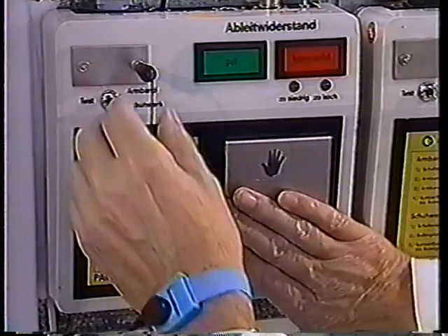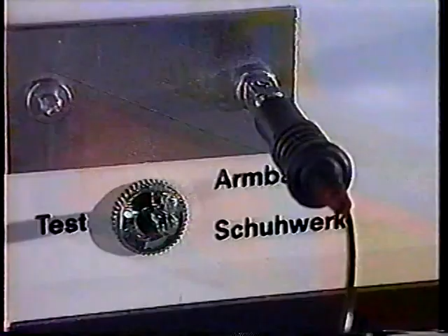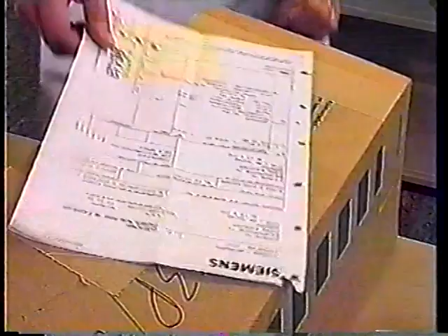In special cases, instructions may be given to wear dissipative finger cots or gloves. The most important item here, however, is the wrist strap, which should always be tested before entering the labeled EPA. As should the ground resistance of the footwear. A heel strap like this one is available for visitors. Of course, we sometimes have problems observing these regulations, but daily routine causes even the most reliable individuals to forget the occasional test procedure. To prevent carelessness from gaining the upper hand, especially in large plants, the gate only opens after the tests have all been passed.